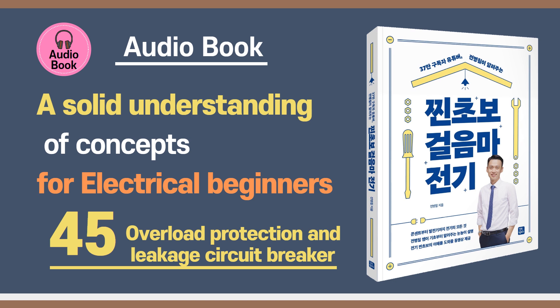That statistic really sets the stage. Most people think of circuit breakers tripping from overload — too many appliances on at once, that sort of thing. But the RCD operates differently. It's all about electrical leakage. In a healthy circuit, the amount of current flowing into something, say your toaster, should be exactly the same as the current flowing out. It's balanced — a perfect loop. The key idea is if those two currents — the in and the out — are not the same, if there's a difference, that imbalance is what the RCD is looking for.